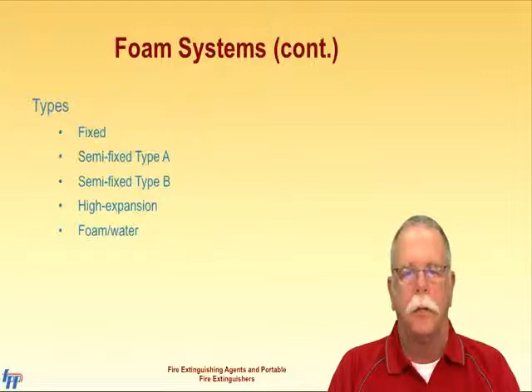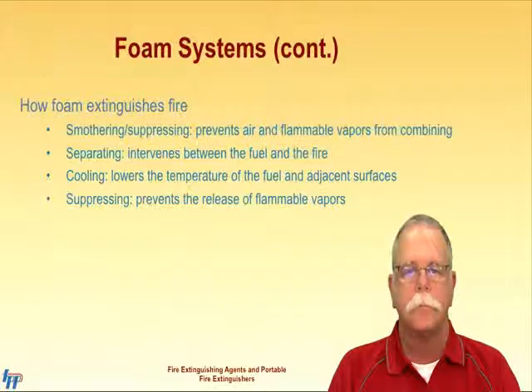A high-expansion foam system is designed for local application or flooding. The difference between a fixed system and a high-expansion foam is the amount the foam expands by the use of a foam generator. A foam water system is similar to a deluge sprinkler system, except that it delivers foam also. Foam extinguishes fire simply by taking away one aspect of the fire tetrahedron.